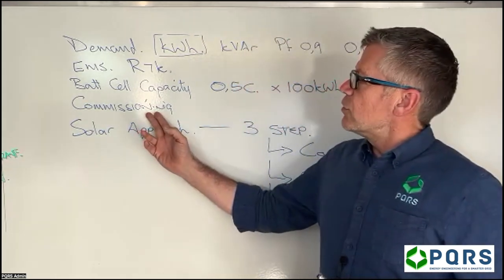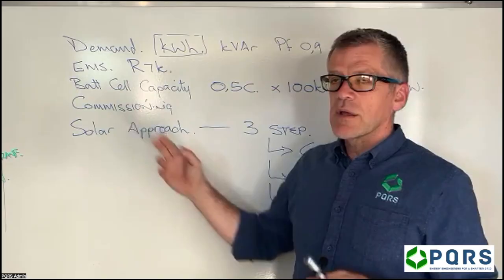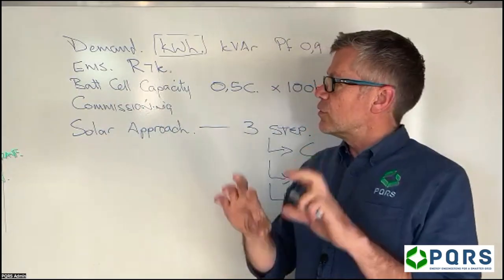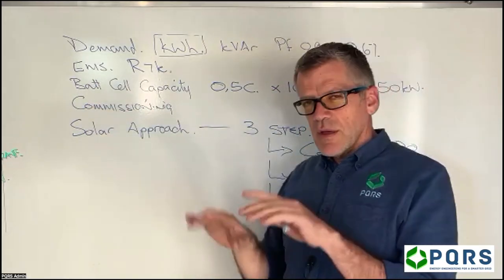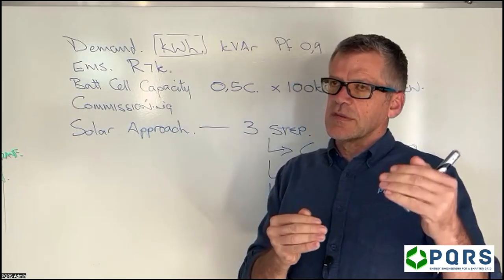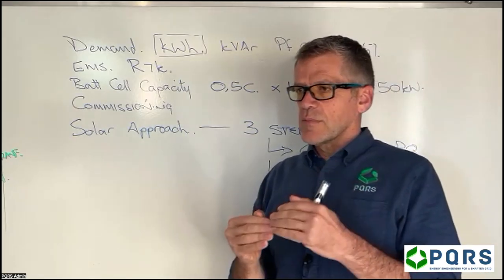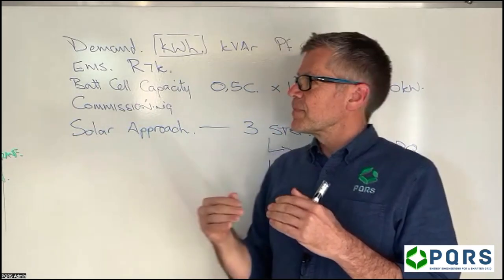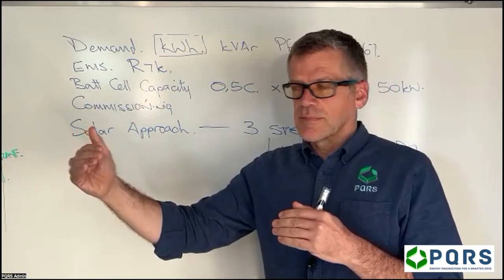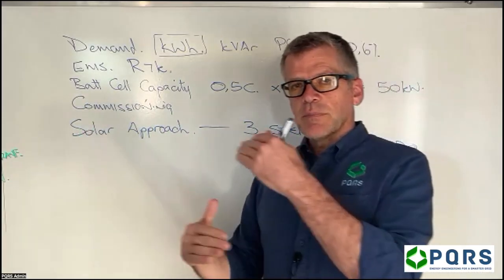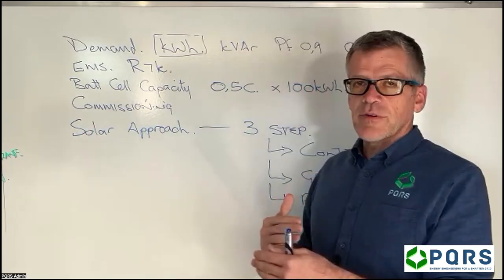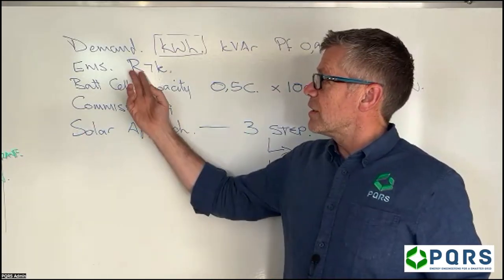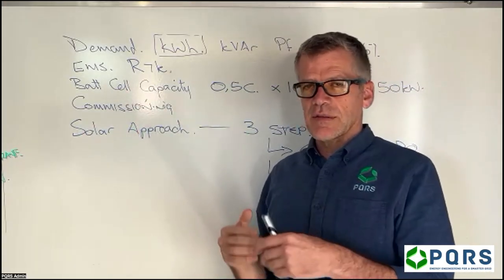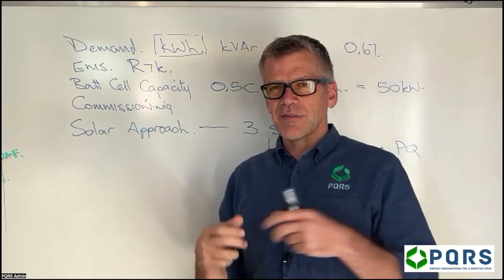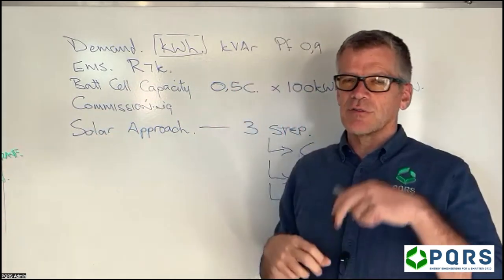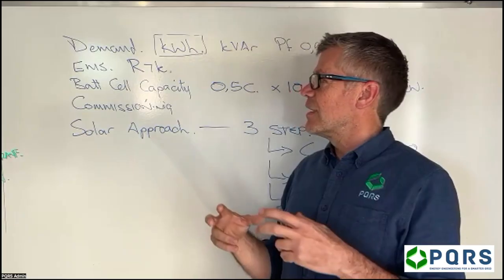So you do the solar installation, and when it gets to commissioning, you set everything up, including the EMS. The process should be that when there's load shedding, the EMS starts up the generator, but for some reason it doesn't. Then you have to fault find and understand why the EMS isn't starting the genset, which usually involves the supplier, so you end up with tech staff coming out to fault find the installation.